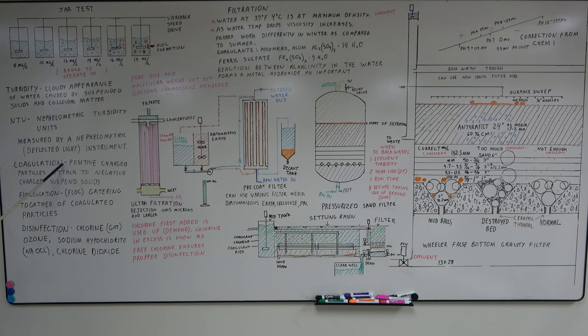Coagulation: you're adding aluminum or ferric sulfate. It's a positive charge of particles attached to a negative charge suspended solids. So basically suspended solids are a negative charge, your coagulants are a positive charge, so it will cause them to stick together. Also the coagulants in the water, they look for a particulate to stick to. So they'll stick on small particles, bacteria and stuff. So the clumping together of the small particles is called flocculation. The slang term is floc. Flocculation is the gathering together of the coagulated particles. This is the result of your coagulation chemicals. They can be really quite large like snowflakes in the water, really impressive, or they can be a very small pinpoint floc. What you do is take the small particles and make them big enough to filter out efficiently.